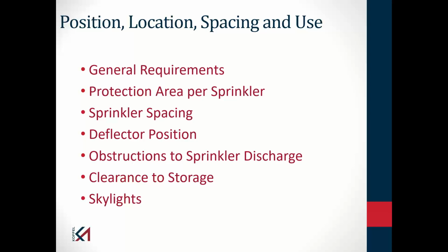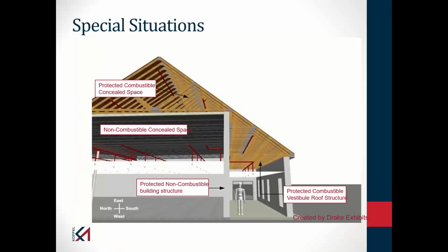Again, think of an umbrella distribution pattern, and you need to get the water distributed over the area that that sprinkler is intended to protect, which takes us back to the second bullet, the protection area per sprinkler. There are also special provisions, depending upon the sprinkler type, that will deal with things like ceiling pockets and skylights. And do you need to put a sprinkler up in those spaces, or are those spaces small enough that they don't require a sprinkler? The last thing I want to talk about with NFPA 13 is that NFPA 13 and the codes that reference NFPA 13 operate under the premise that sprinklers will be everywhere in your building, unless NFPA 13 provides language that says sprinklers are not required in certain spaces.